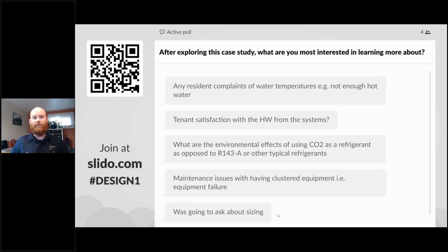And then sizing, yeah, we're definitely going to get into sizing in session 2, but we can essentially trade off how much heat capacity the heat pump has with how much storage we're providing for the system. So that storage tank is our thermal battery. We can think of it just as an electrical battery. If we make it bigger, we can essentially serve more of the load from that battery alone. Our heat pump, we can think of as our solar panels. And so we can have a small trickle charge, charging that battery throughout the day, and that works as long as we don't get 2 peak loads right next to each other.